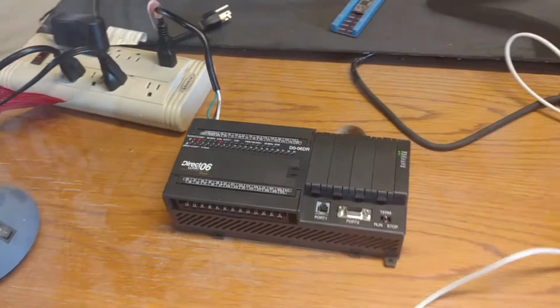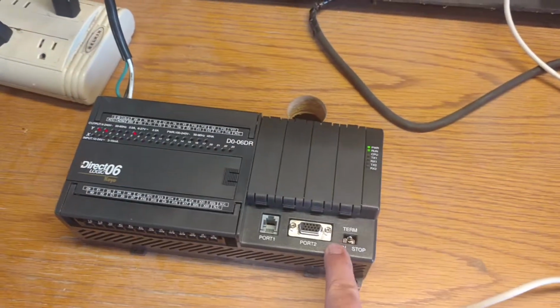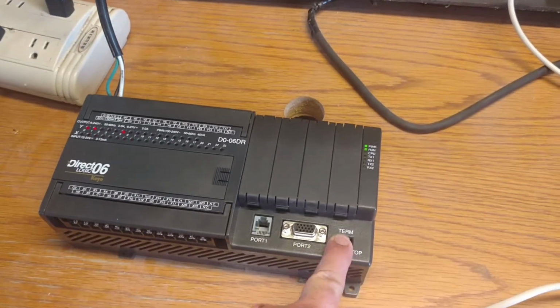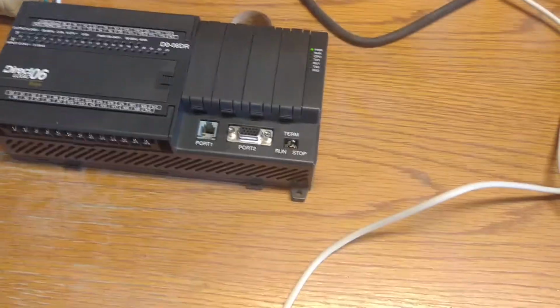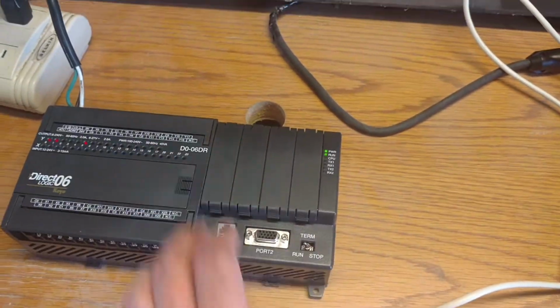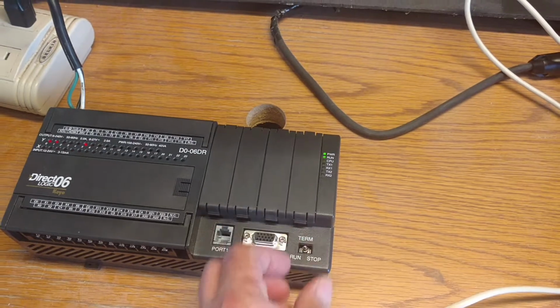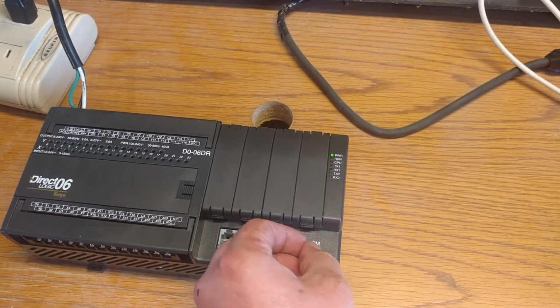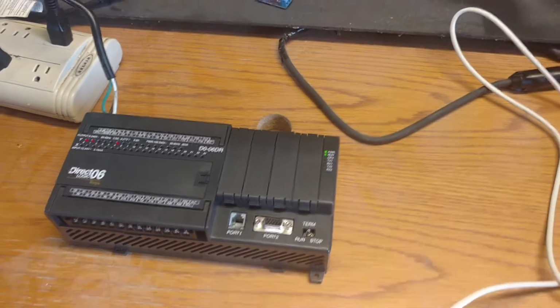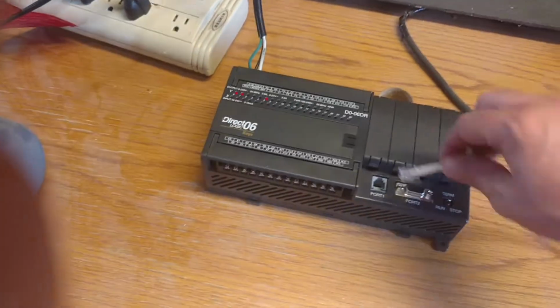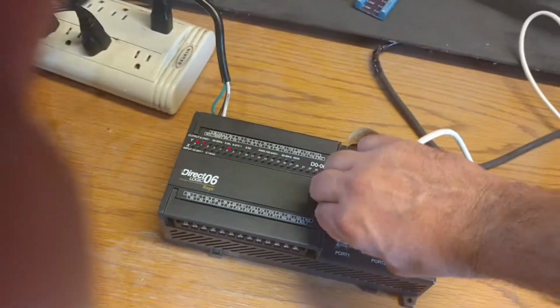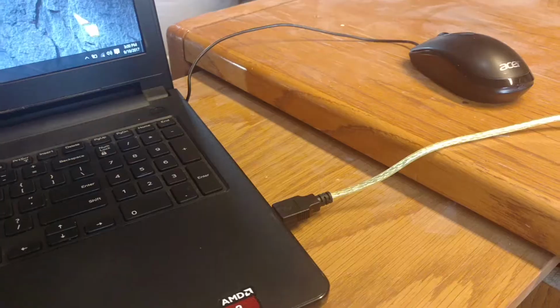The first communication issue you might have is your little switch here. You do not want your little switch in stop. You do not want your little switch in run. If you're having issues, just put that thing right to terminal. So I'm going to go ahead and make sure it's right in the middle on terminal. Go ahead and click, put in my RS-232 wire there. Go ahead and follow that down to the adapter. Grab my USB. Go ahead and plug in your USB.